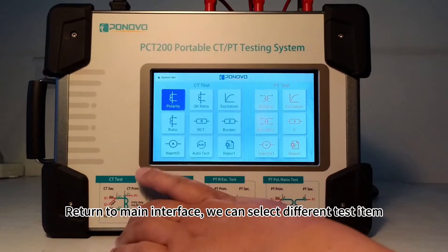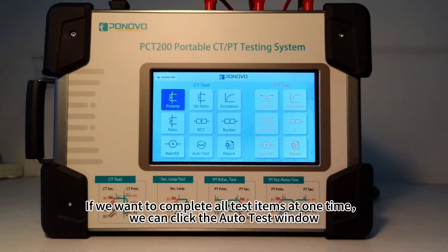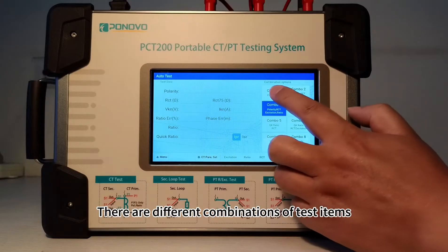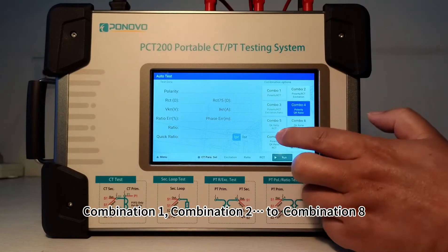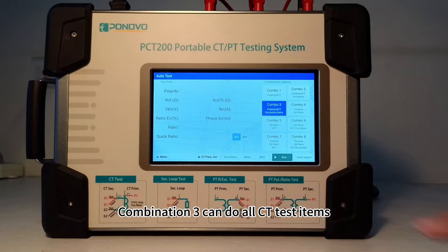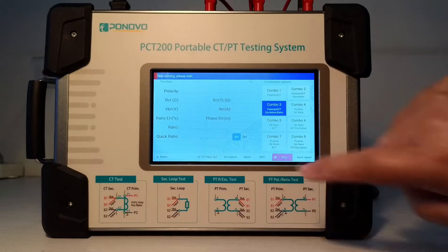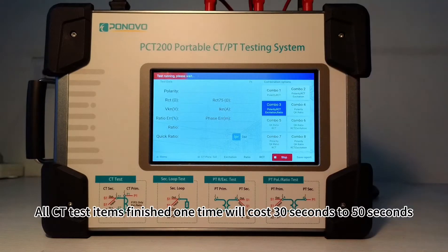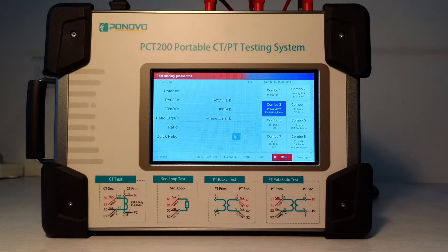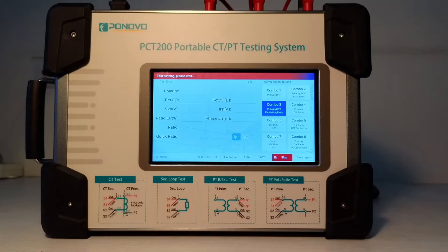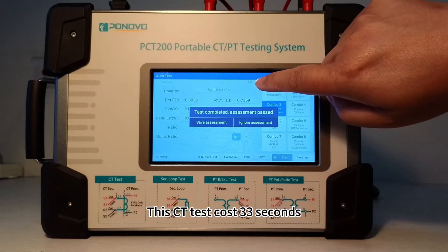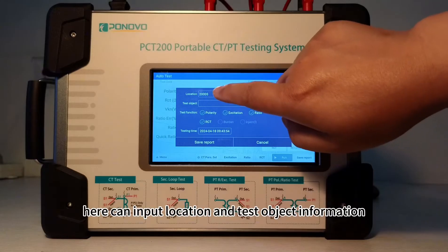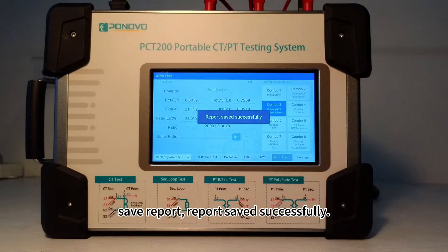Return to the main interface. If we want to complete all test items at one time, we can click the auto test window. There are different combinations of test items — Combination 1, Combination 2, through Combination 8. Combination 3 can run all CT test items. Start to run. All CT test items finished in one session will cost 30 to 50 seconds. This CT test costs 33 seconds. Test completed — assessment passed. Save assessment. Here you can input location and test object information. Save report — report saved successfully.